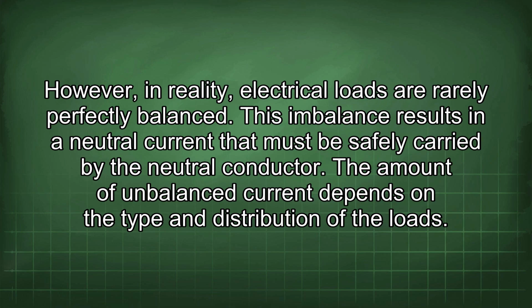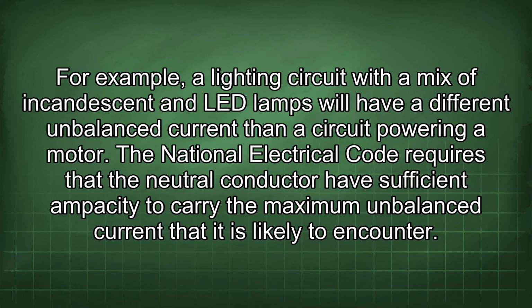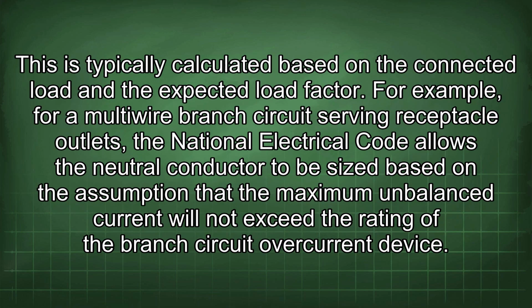The amount of unbalanced current depends on the type and distribution of the loads. For example, a lighting circuit with a mix of incandescent and LED lamps will have a different unbalanced current than a circuit powering a motor. The National Electrical Code requires that the neutral conductor have sufficient ampacity to carry the maximum unbalanced current that it is likely to encounter. This is typically calculated based on the connected load and the expected load factor.